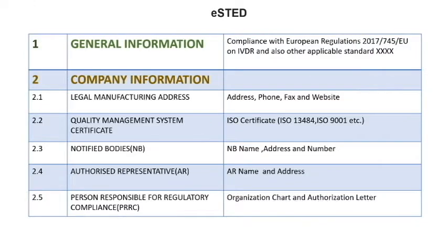General information consists of regulations. Here we can write that the purpose of the STED file is to show the compliance with the requirements of European Regulation 2017/746 EU on in vitro diagnostic medical devices, IVDR, and also other applicable standards. Other applicable standards, for example, RoHS directive, radio equipment directive, REACH regulation, etc.